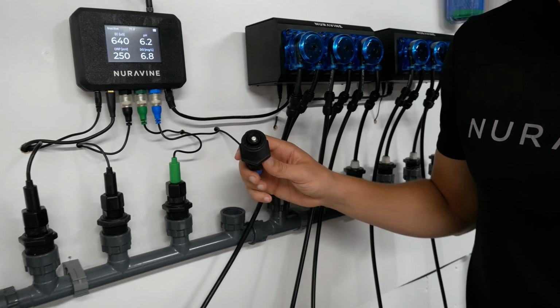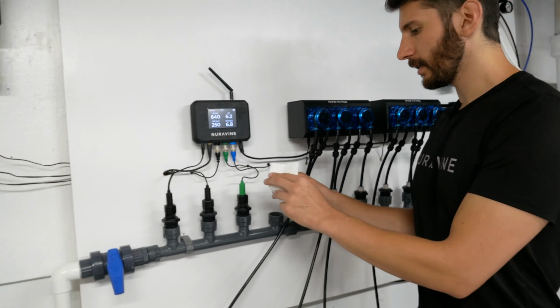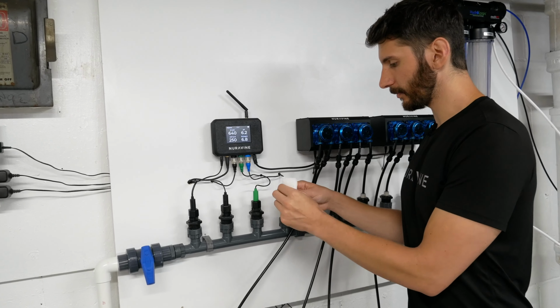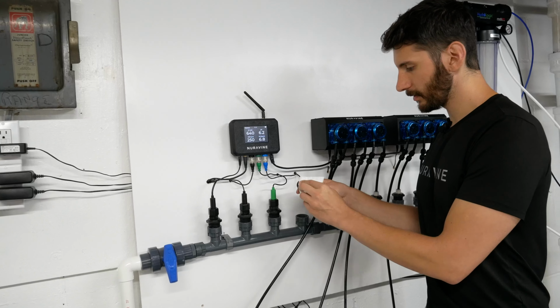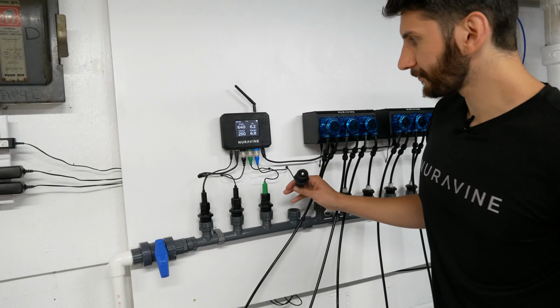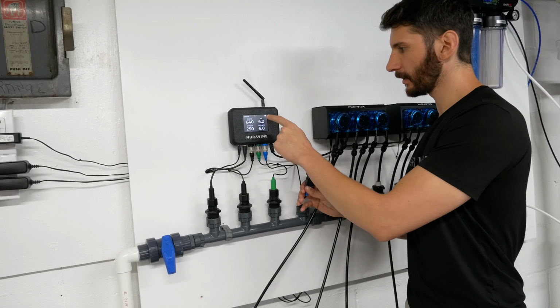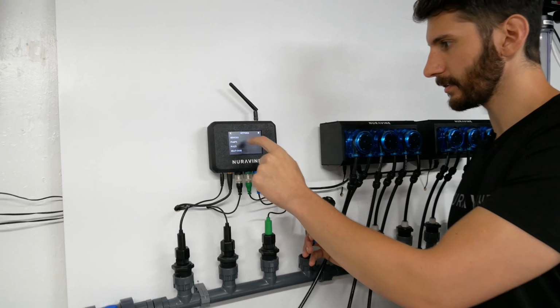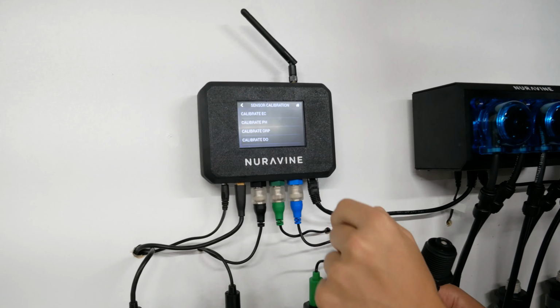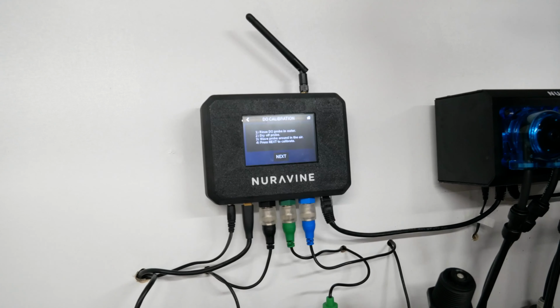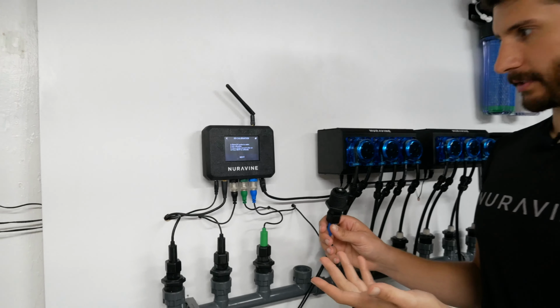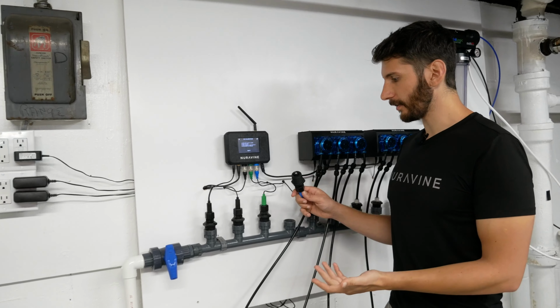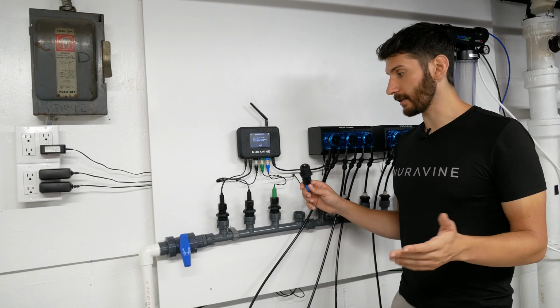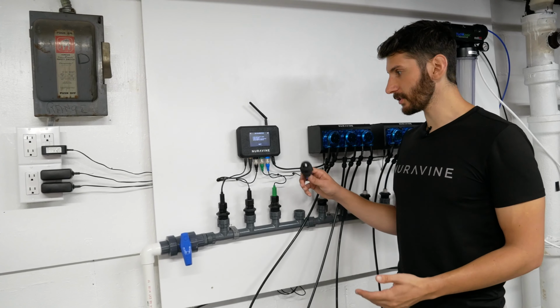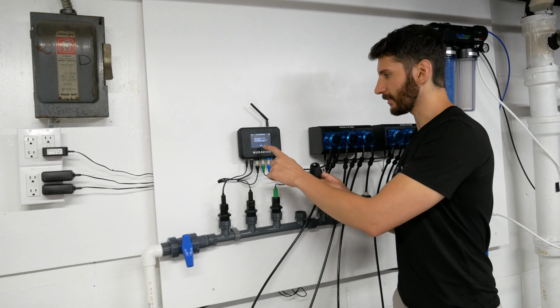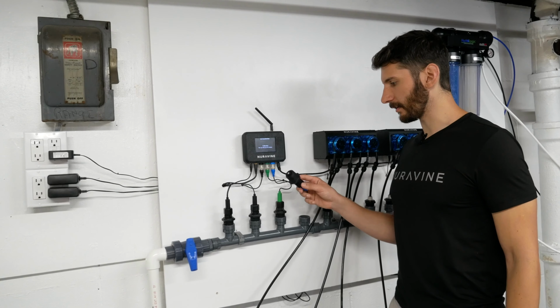So what I'm going to actually do is I'm going to give it a little bit of a wipe down. You don't have to worry too much about this. This is a pretty sturdy probe. So now that this is nice and clean, we're going to head over to the menu and then go back to sensors, click on Calibrate, and then hit Calibrate DO. Now we've already followed the instructions on screen. We've cleaned it in water, we've dried it off, and this one's different. It's a lot easier because you don't even need to put it into a solution. So we're actually just going to wave it around in the air. So I'm going to click next, and we'll just kind of move it around a little bit.